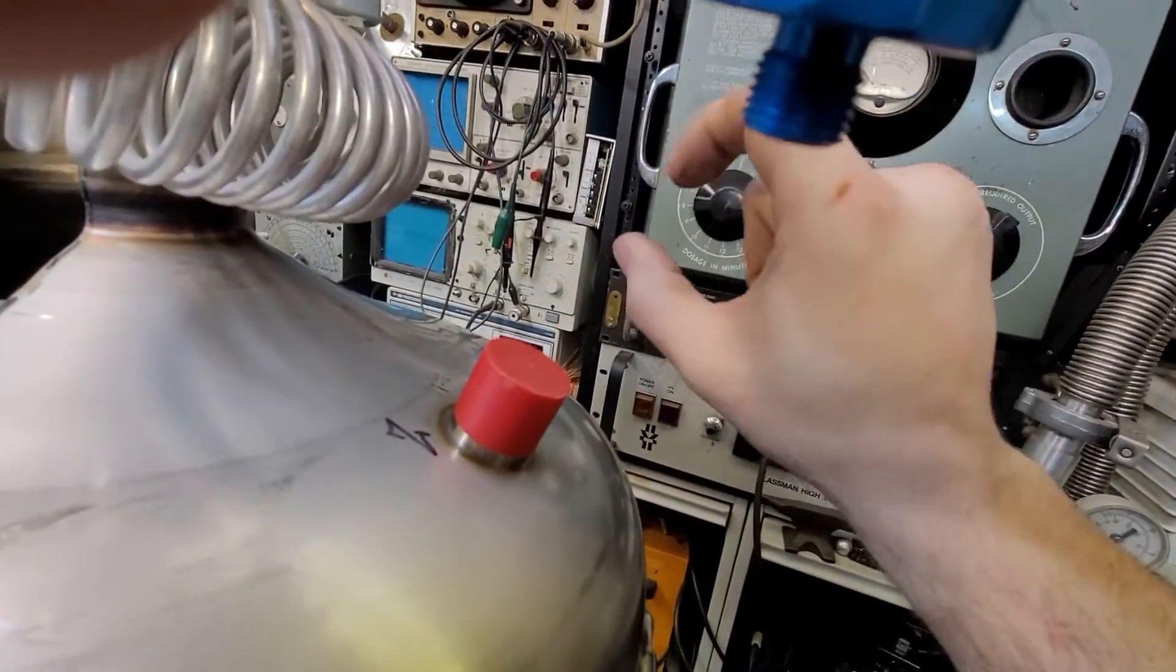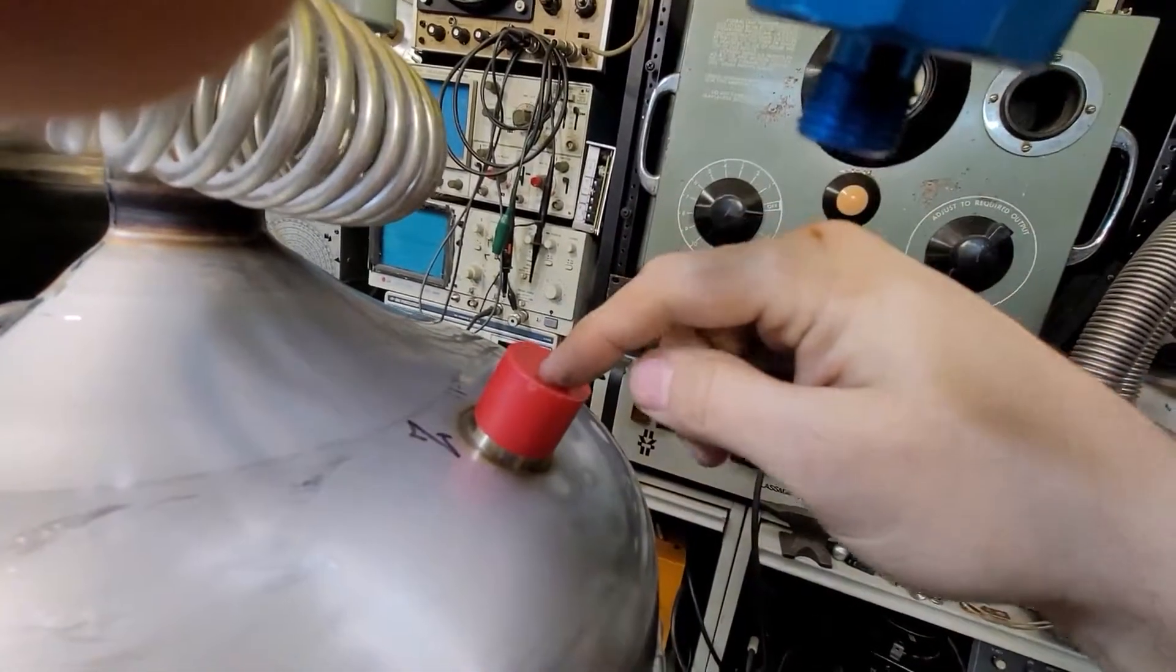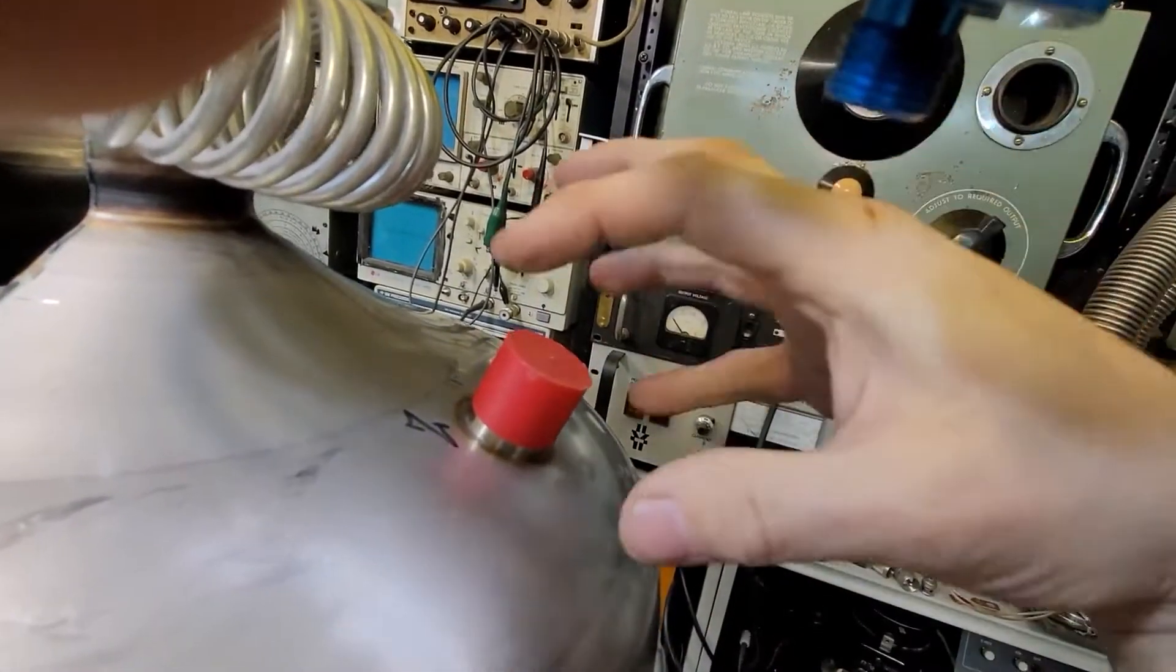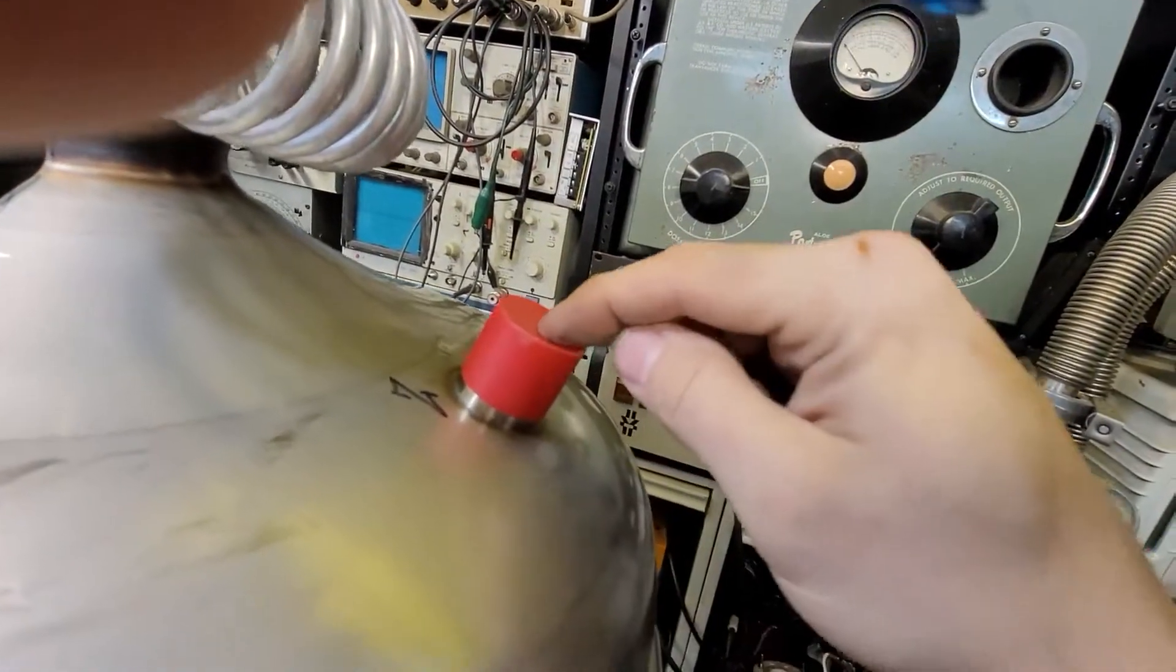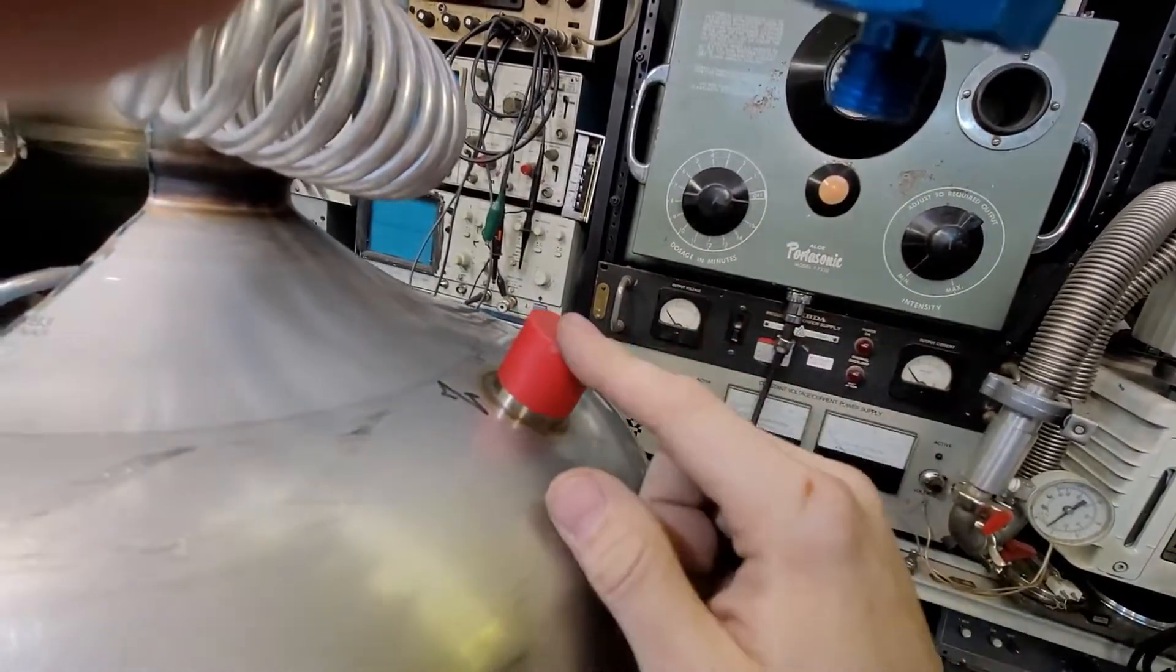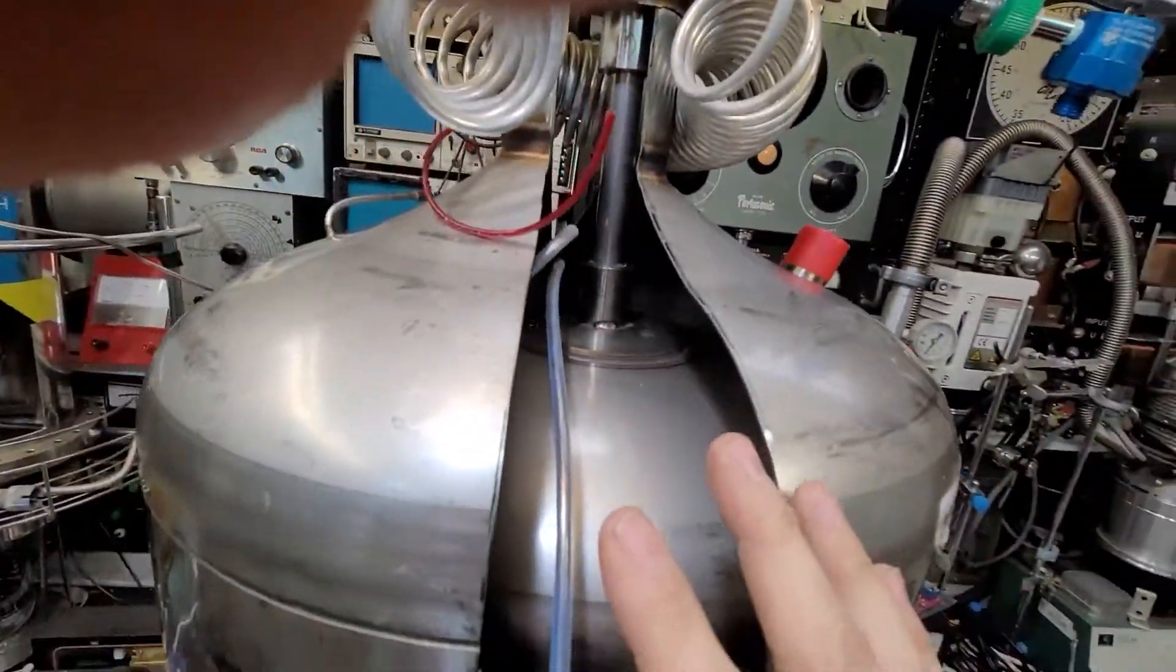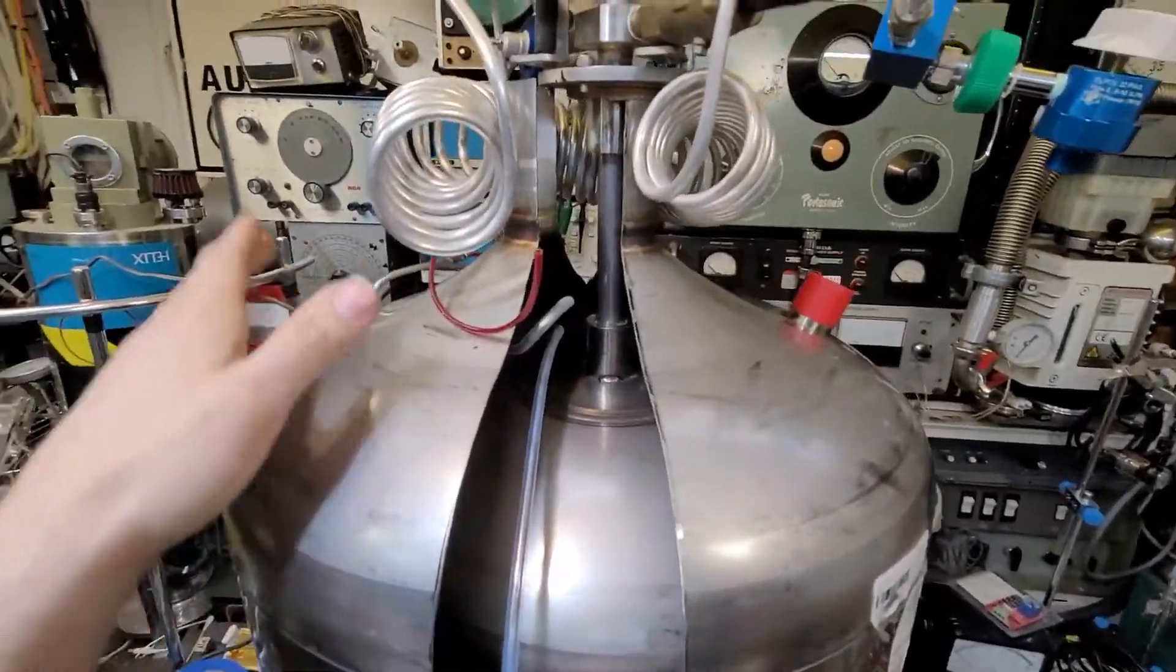Once they've achieved that, there's a special rod inside that releases the plug down into the hole. And it pulls that inside. And then once they release the atmosphere out here, that plug gets sucked in or pushed in from the outside atmosphere to seal that hole. And they put some vacuum grease in there to basically fill in any imperfections. And it is now sealed. So that maintains a vacuum inside this tank for the duration of its life.